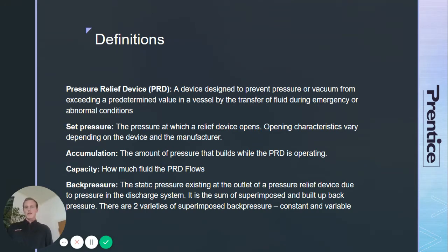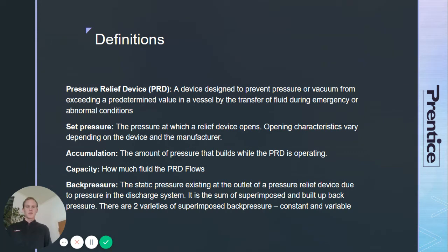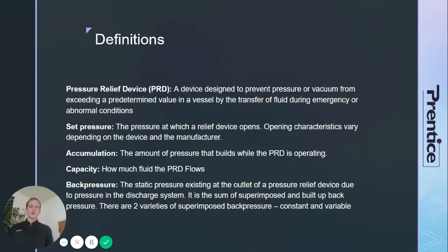Set pressure is the pressure at which the device opens — opening characteristics vary depending on the device and the manufacturer. Accumulation is the amount of pressure that builds in the vessel while the device is open, after you've reached your set pressure. Capacity is the amount of fluid that flows per unit of time through the device, and back pressure is the amount of pressure that exists at the outlet of the device.